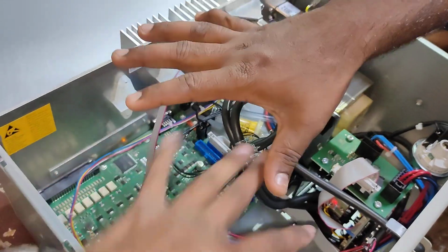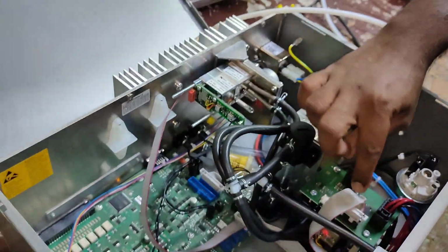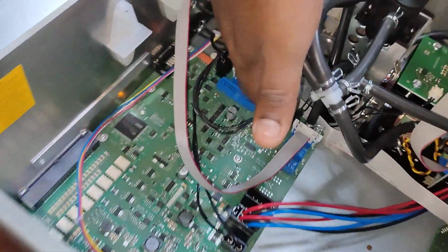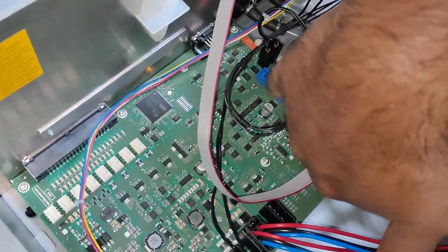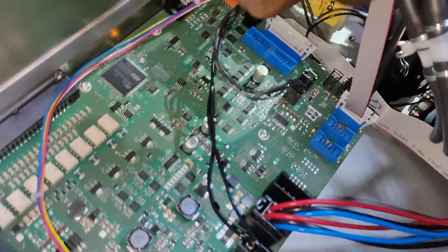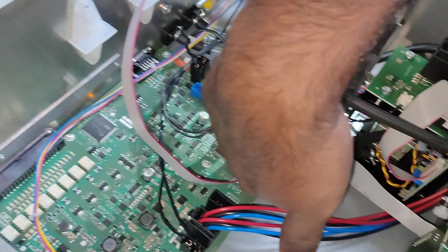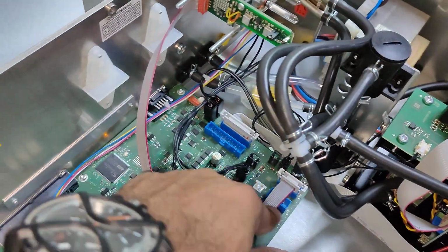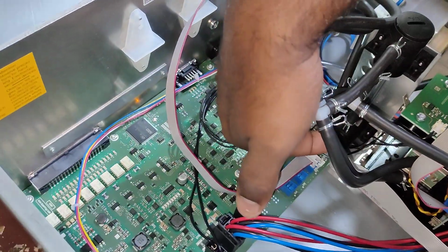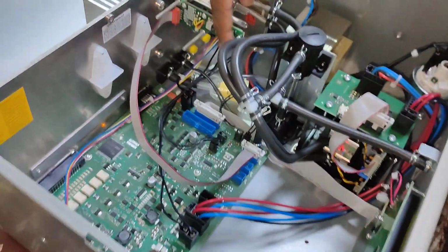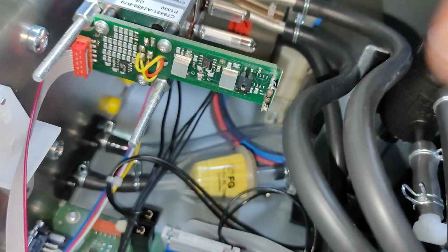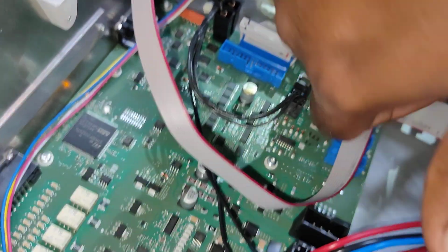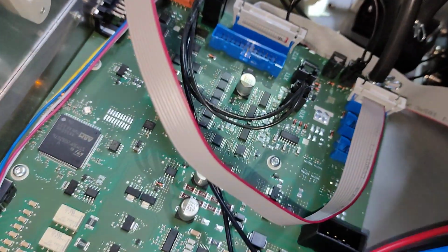Is this PCB only for CO? No, this motherboard is for both CO and O2. Now this sensor signal is also going to the motherboard. There are three channels. It can take 3 IR, but we are using only one for CO. If any problem comes on this side, we can change this one also. Every channel is defined based on the jumper. This jumper means channel 1, and this motherboard is configured for channel 1 as CO. So you have to connect only X35. You have 35, 36, 37, and you have to connect in this location only.